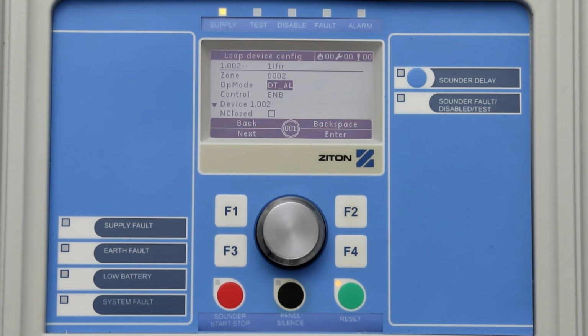DTAL stands for Disable Inputs with Technical Alarms. Select this option if you want an input unit to disable all the technical alarm inputs, both latched and unlatched. PREAL stands for Pre-Alarm. Select this option if you want an input unit to display a pre-alarm when activated. MSP stands for Sprinkler. Select this option if you want the input unit to display a sprinkler condition when activated. The mode will also display a fire condition on the panel when activated.